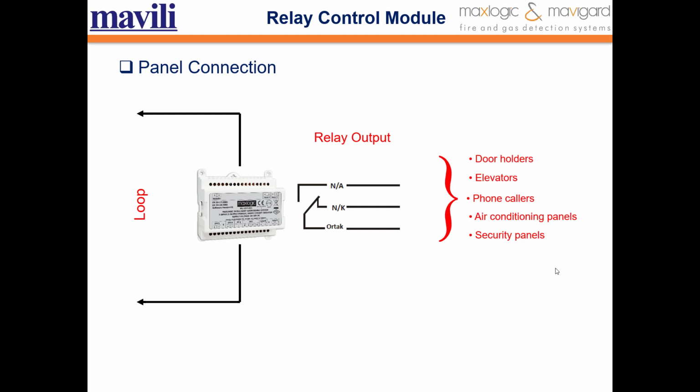It can be set with the computer program to output according to the type of event determined by the user. Also, 13 different event types can be assigned, and a delay of up to 250 seconds can be set for the outputs via the computer program. If no adjustments are made, the delay is 0 seconds, and the event type is set to fire and fault alert.